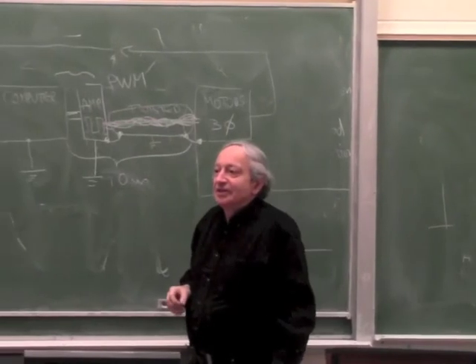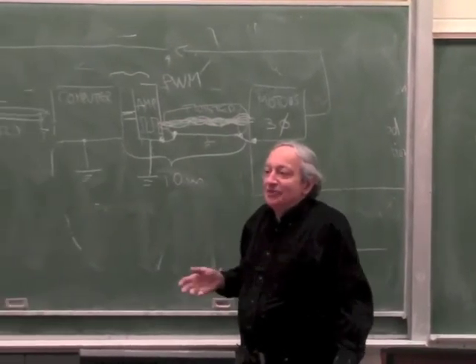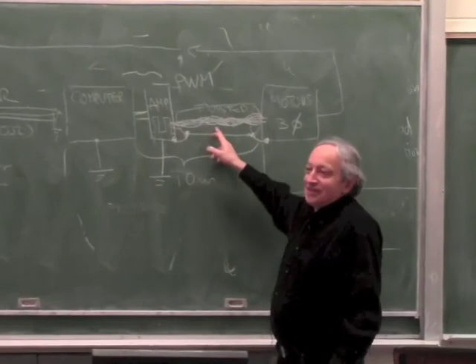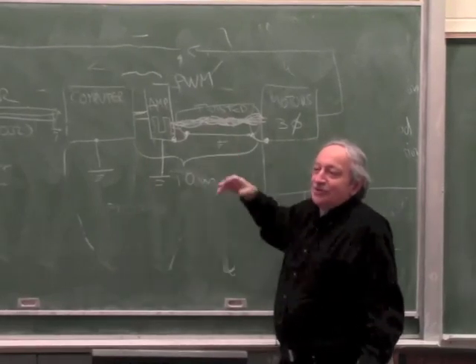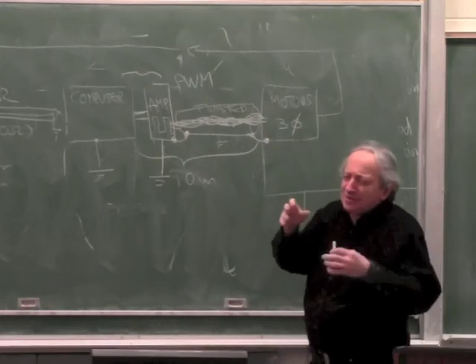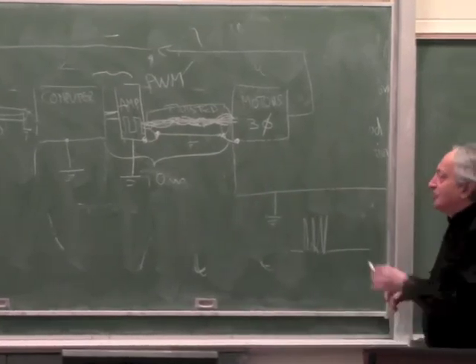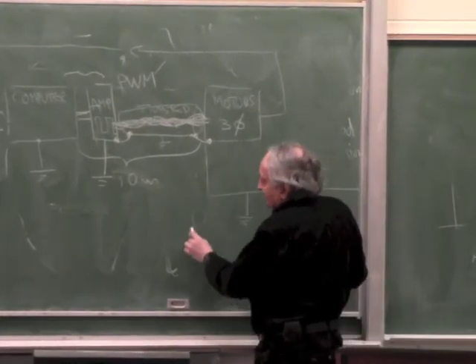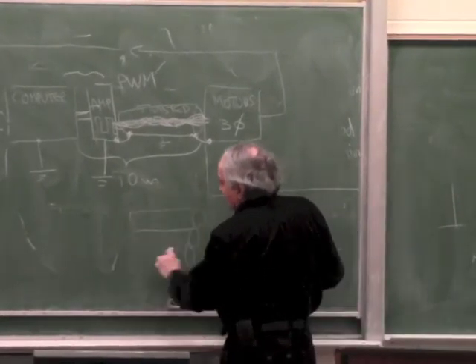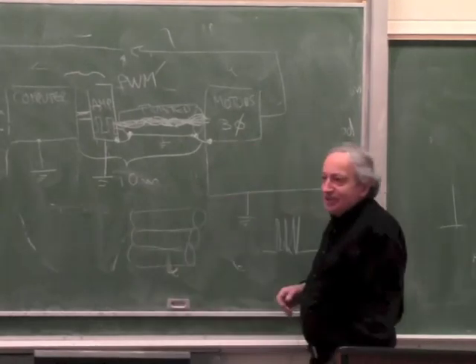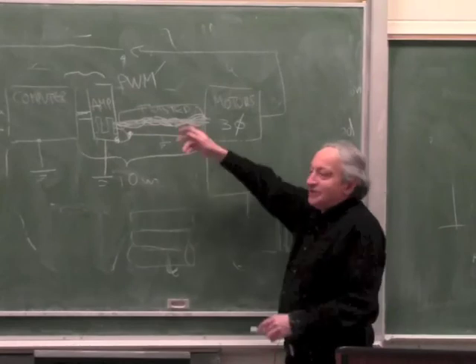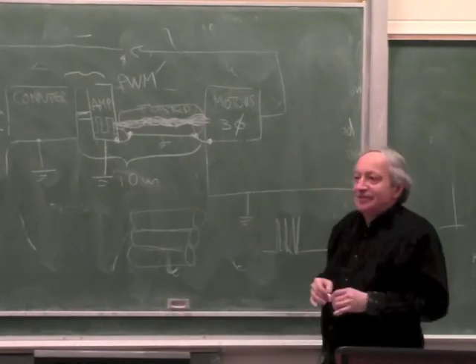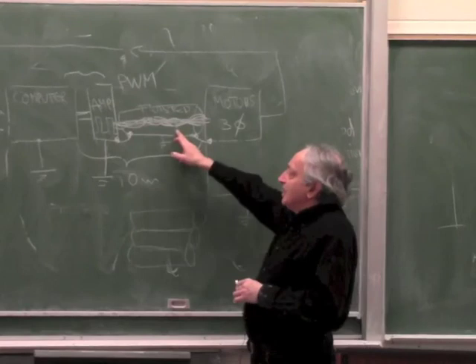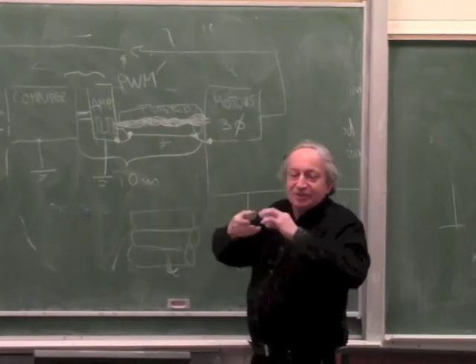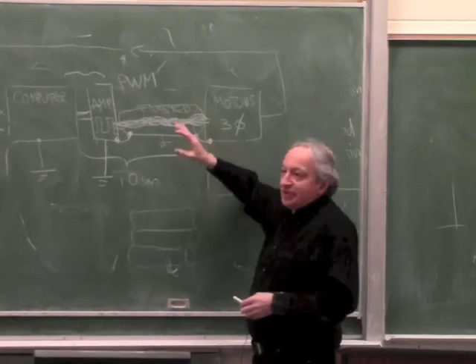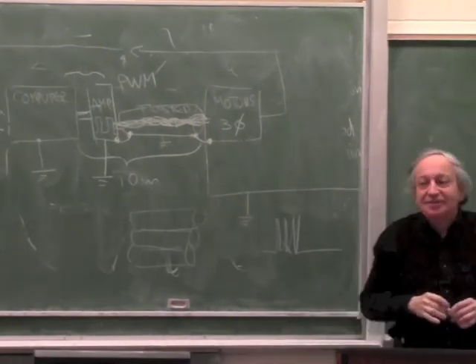Would it be an advantage to use a coax cable instead? You couldn't buy a coax cable with 3 wires inside — it's just not standard. You could buy one with heavy conductors, but it would be very expensive. You could use 3 separate coaxes instead of 3 phases, but that actually wouldn't be best, because then they aren't twisted together. So in the end you don't do that — you use a regular electrical cable, a twisted triplet, but with a shield. It's very important to remember the shield, because it's switch mode.